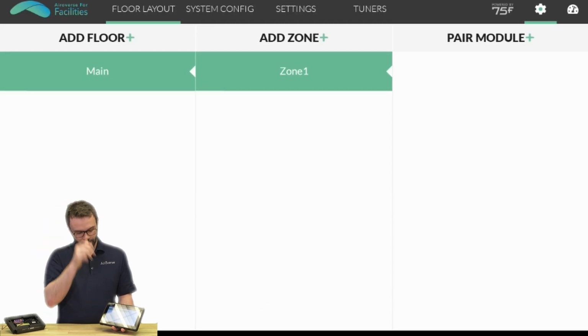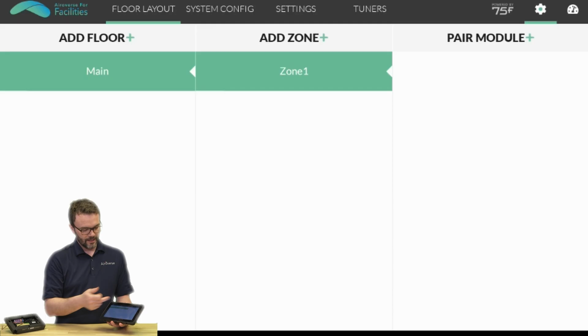Following the green line here, if I go Main, Zone 1, now I can pair a module to Zone 1. But before we pair anything, we have to define what this central control unit is going to be used for—that's what we consider the system config.